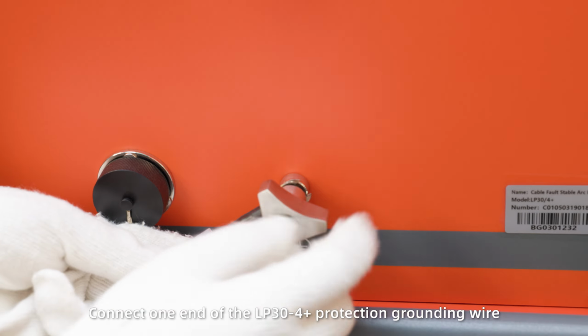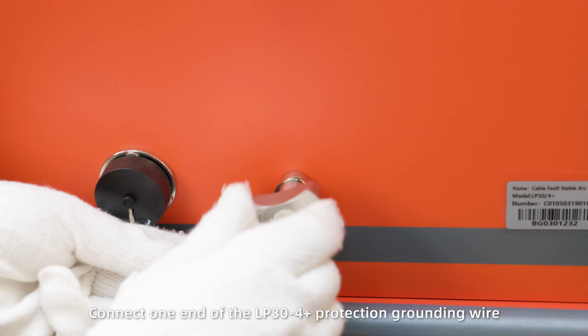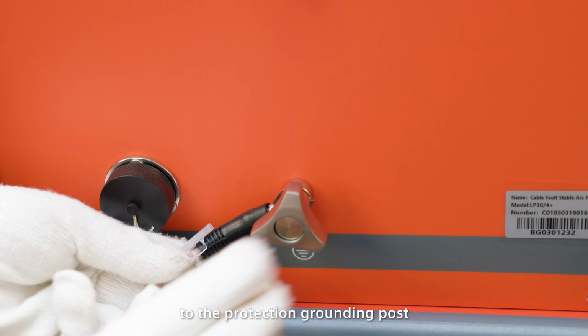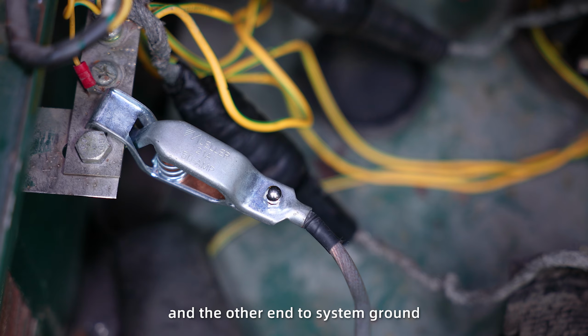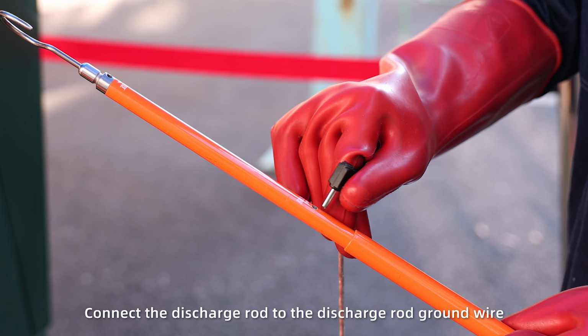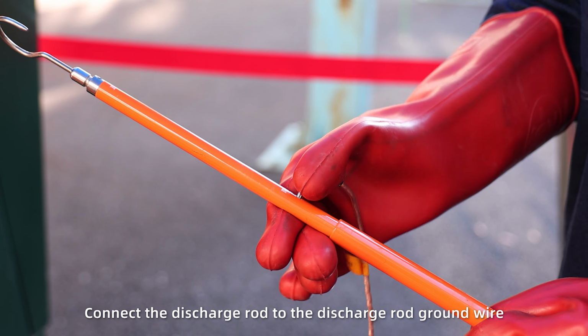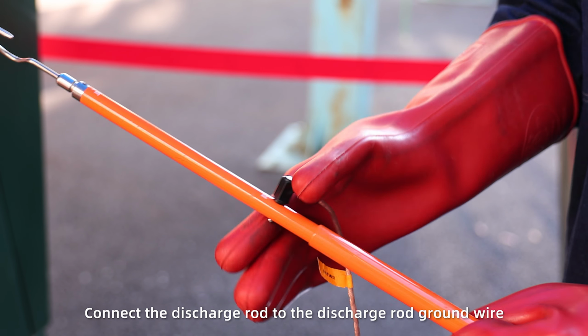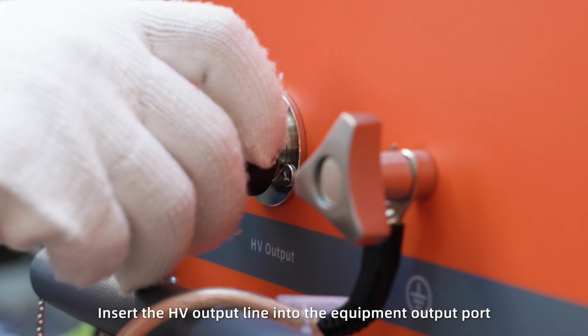Connect one end of the LP30-4 Plus protection grounding wire to the protection grounding post, and the other end to system ground. Connect the discharge rod to the discharge rod ground wire. Connect the other end to system ground. Insert the HV output line into the equipment output port.